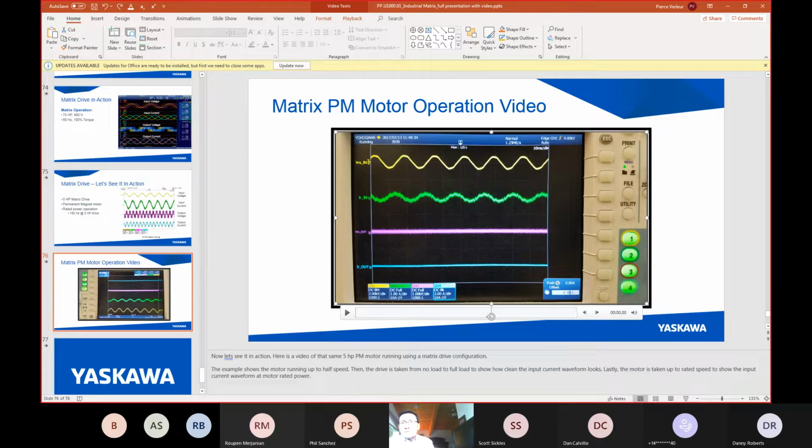As a result, when you're talking about high impact loads, I want to be in that conversation with you. I want to help you size the matrix drive properly. This is not a defeating circumstance. This is a circumstance that needs to be properly engineered. And we may oversize in those circumstances once we understand the dynamics of the load. But in dynamic load situations, we cannot just go ahead and apply the matrix drive without reasonable analysis. So that's point number one.